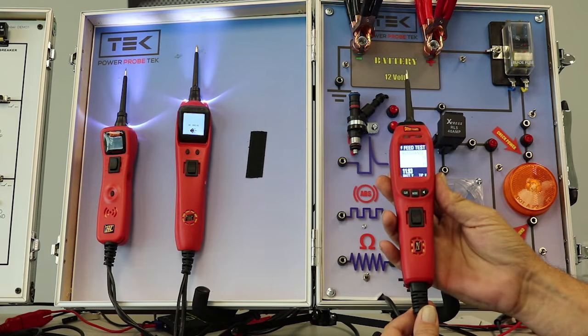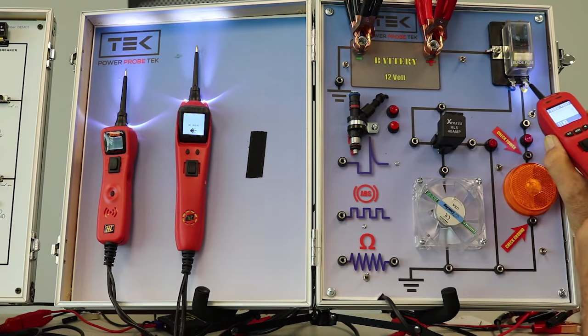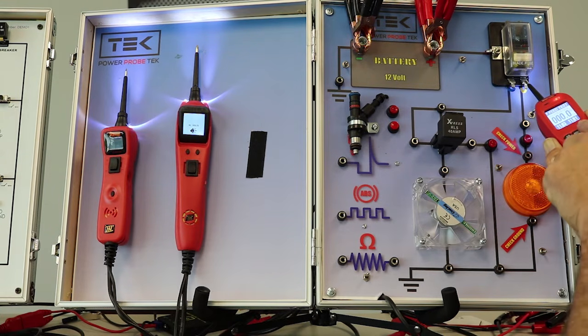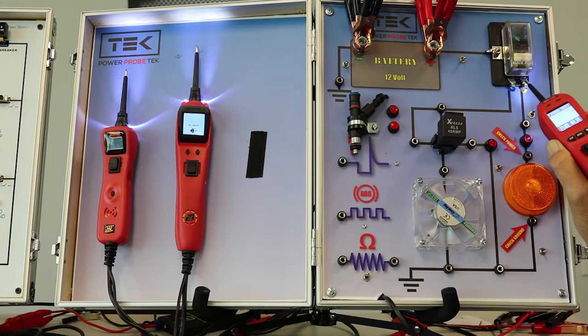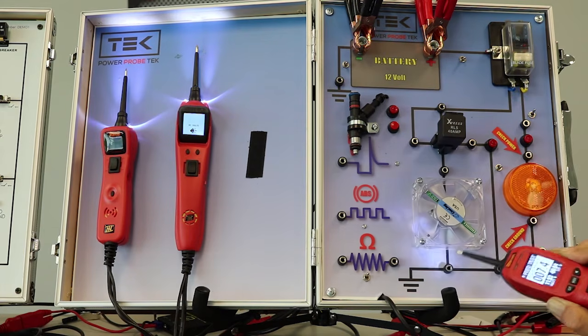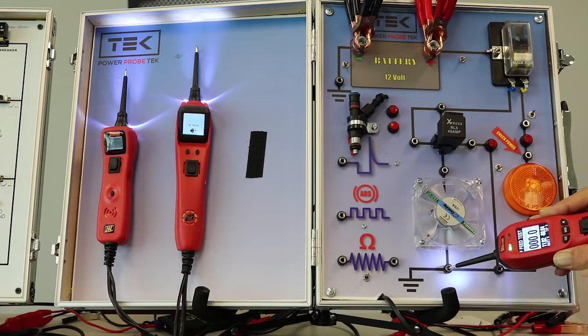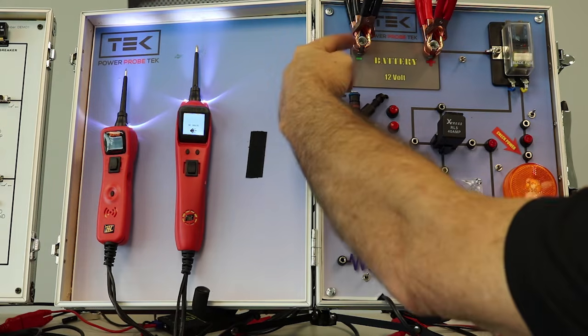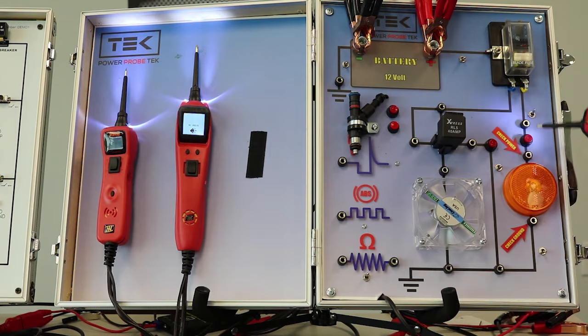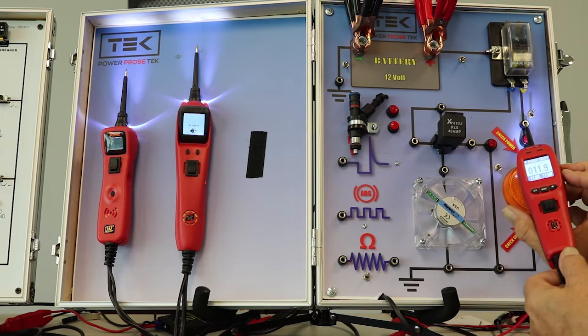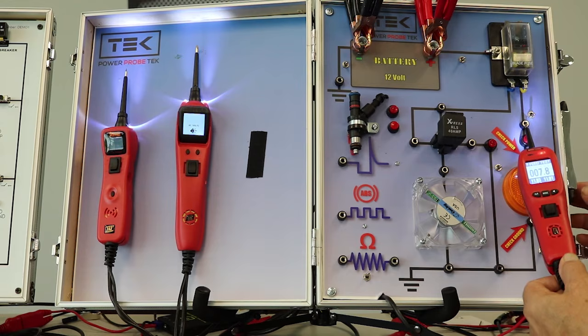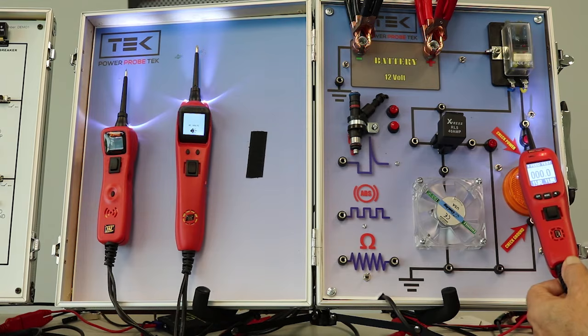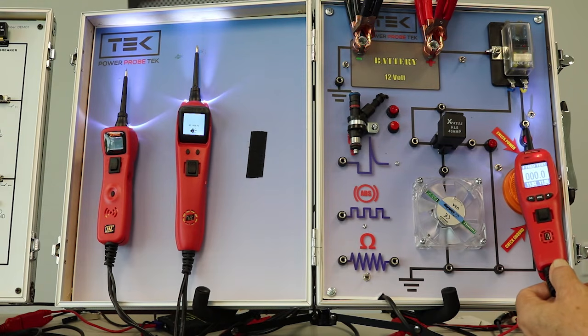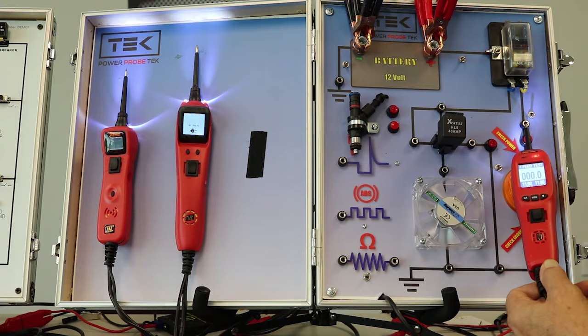What is kind of unique, and why we call this feed test and not ohm meter, is that I can actually tap into live circuits with voltage on it. If that speaker's on, you'll get that tone, but if it's a live circuit, you will either get the red or green light. Green light means that resistance number is from the battery negative to wherever you are in the circuit - oh, I got a voltage drop. Red light is from the battery positive to wherever you are in the circuit. You're actually able to take live resistance readings in active live circuits.